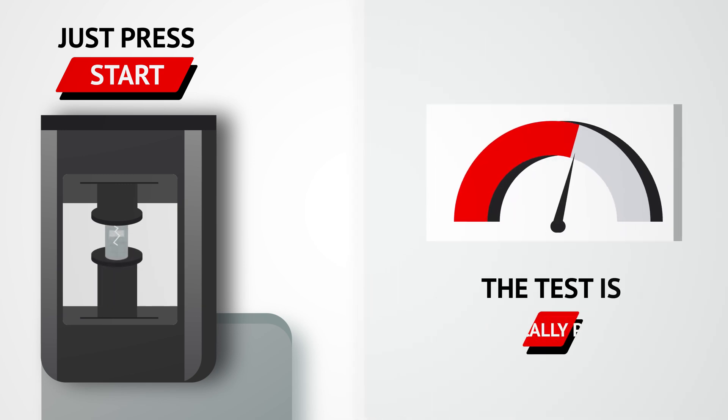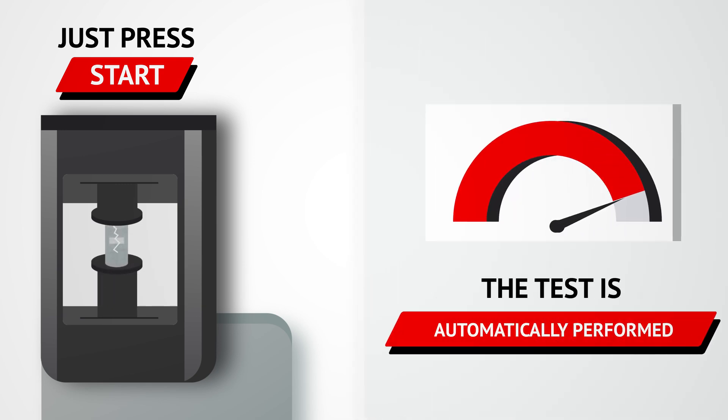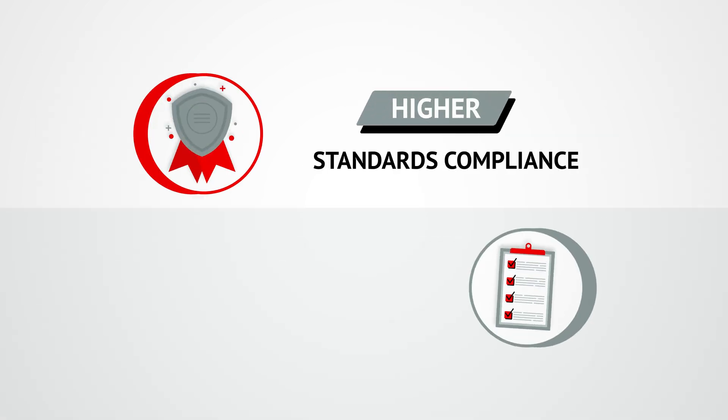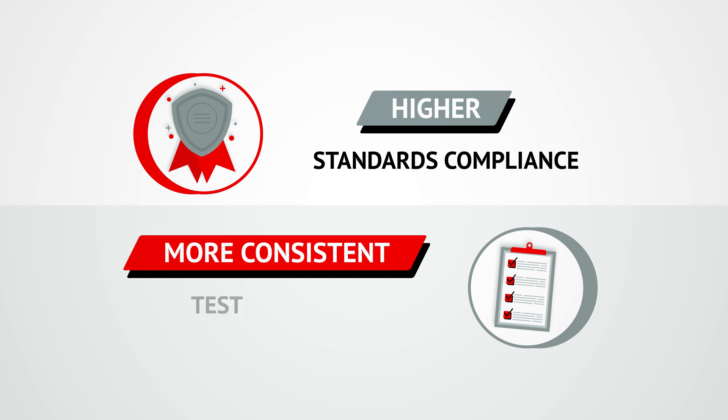Operation of your automatic compression machine is quick and easy. All you need to do is press the start button. The test is automatically performed at the correct loading rate, according to a preset test procedure, achieving the highest level of standards compliance and consistency in test results.